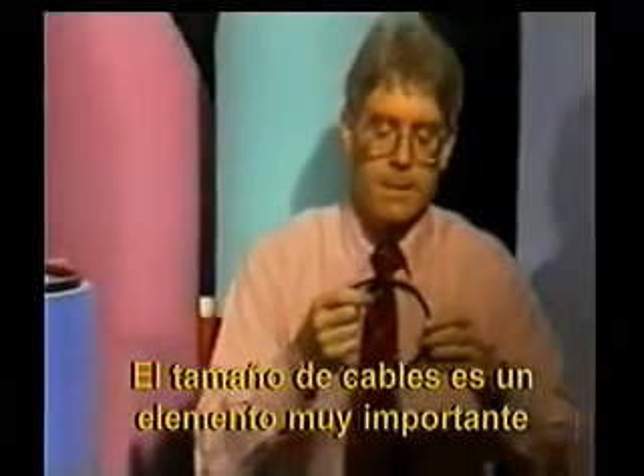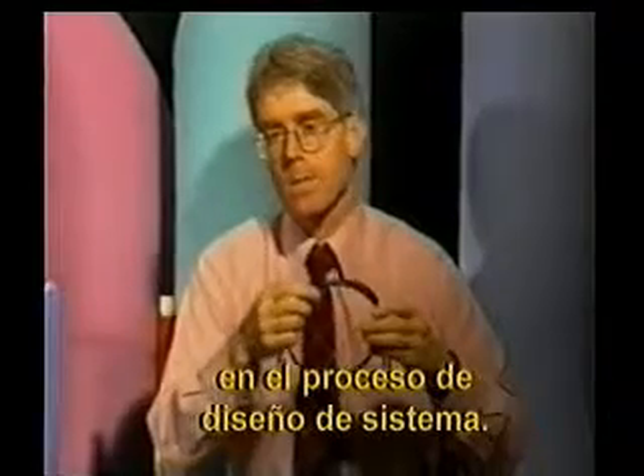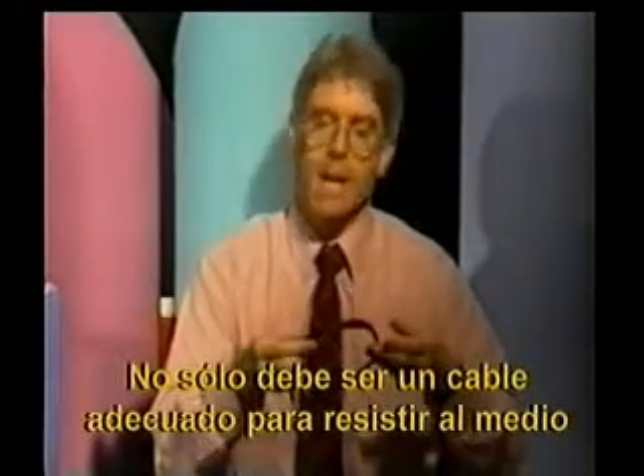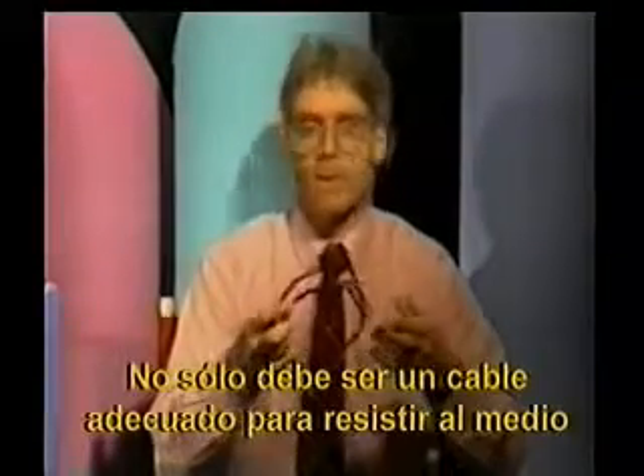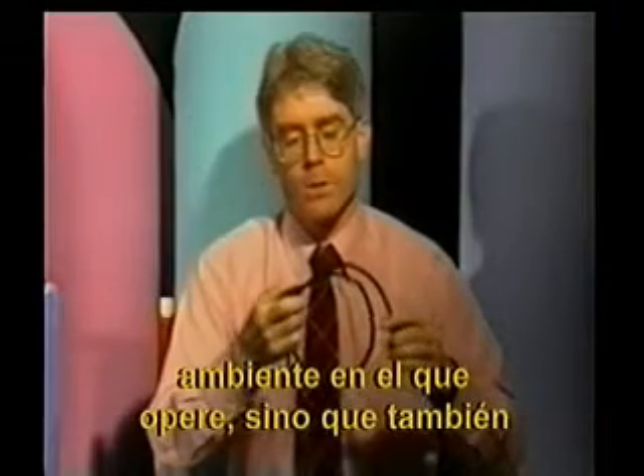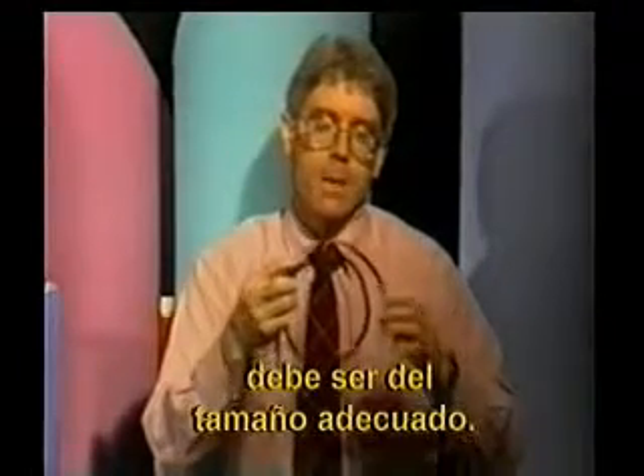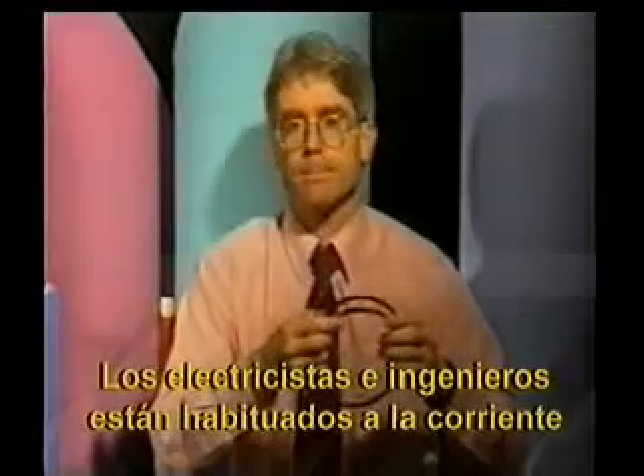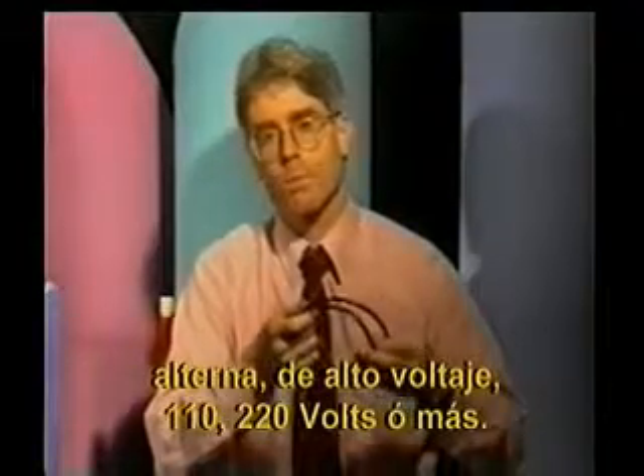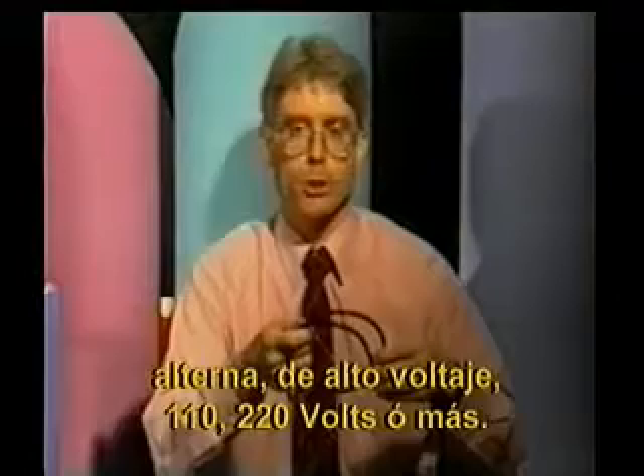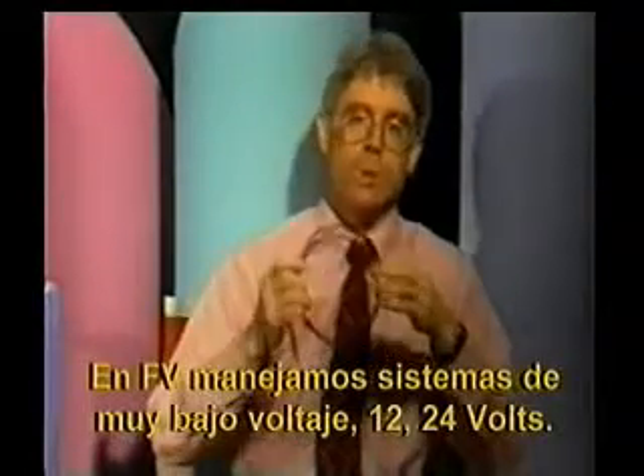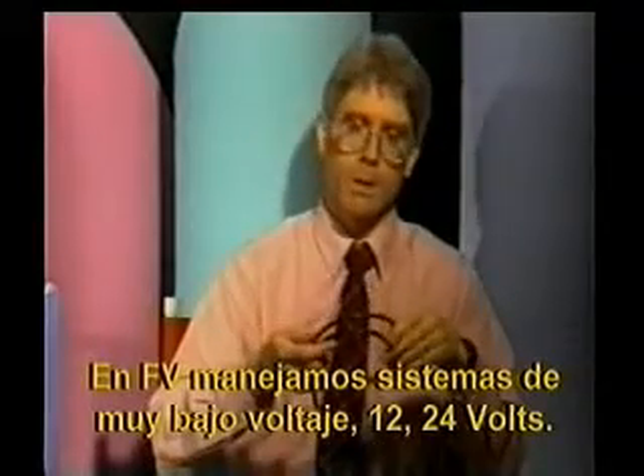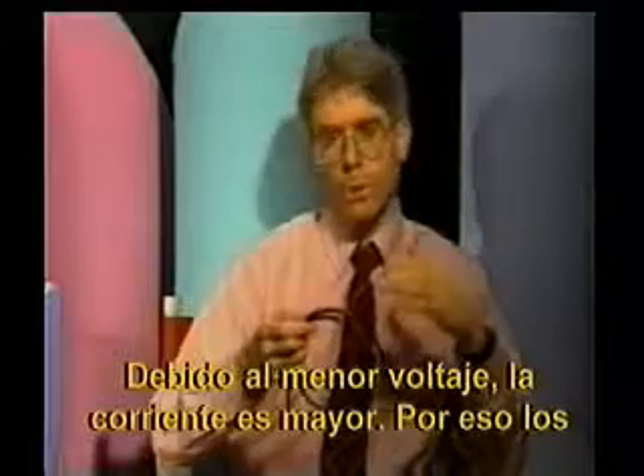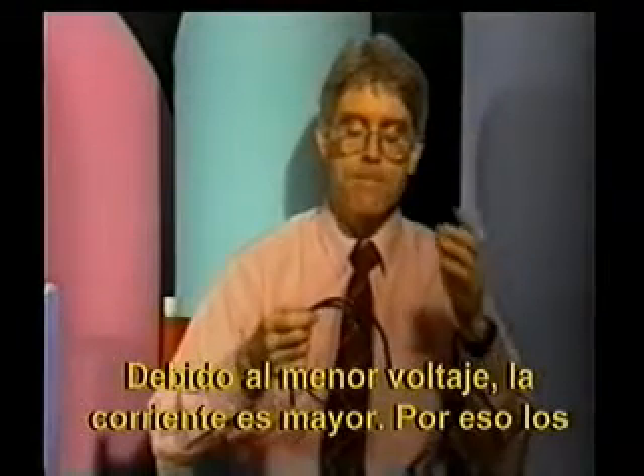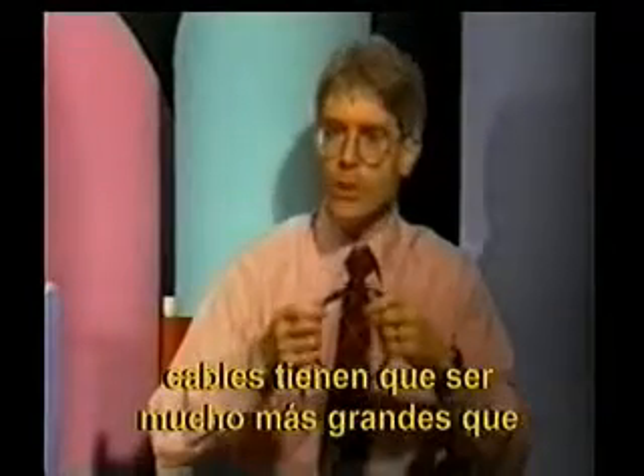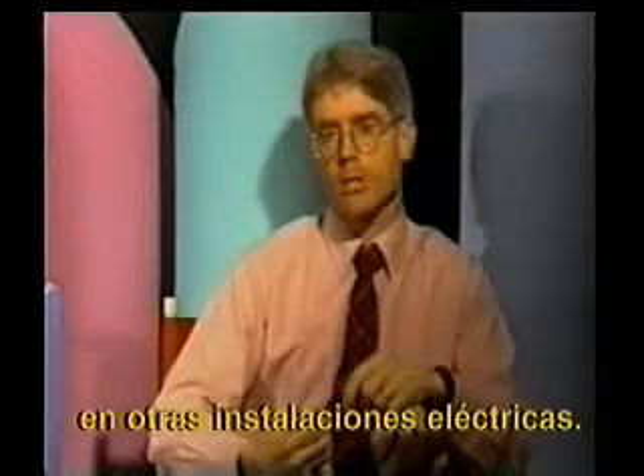Wire sizing is a real important element of your system design process. We not only have to choose proper types of wire that will resist the environment that they might be operating in, but we've also got to choose the right size of wire. We're often dealing with electricians or engineers that are used to dealing in the AC world, relatively high voltage world, 110, 220 volts or higher. In photovoltaic systems, we're often dealing with very low voltage systems. 12 volts, 24 volts are typical. Because of the lower voltage, we have higher current. That leads to us needing to choose much larger wires than most other electrical installations are used to.